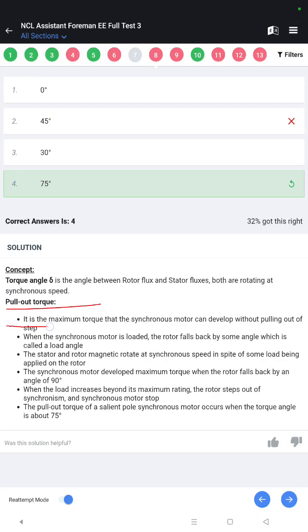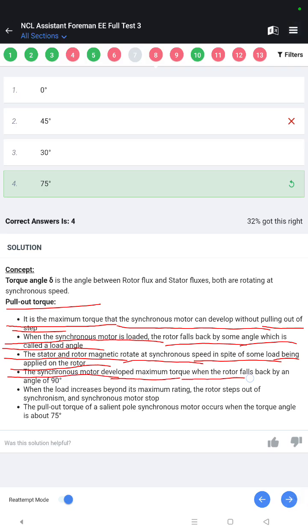Pull-out torque. It is the maximum torque that a synchronous motor can develop without pulling out of step. When the synchronous motor is loaded, the rotor falls back by some angle, which is called the load angle. The stator and rotor magnetic fields rotate at synchronous speed in spite of some load being applied on the rotor. The synchronous motor develops maximum torque when the rotor falls back by an angle of 90 degrees. When the load increases beyond its maximum rating, the rotor steps out of synchronism and the synchronous motor stops. The pull-out torque of a salient pole synchronous motor occurs when the torque angle is about 75 degrees.